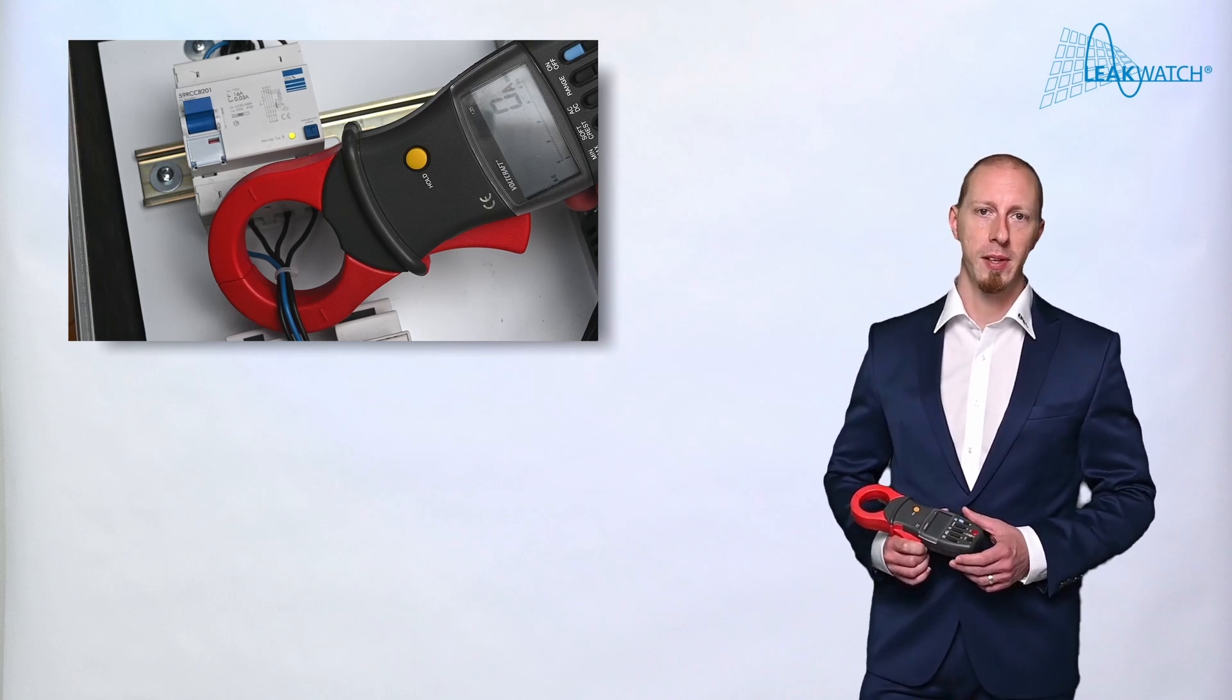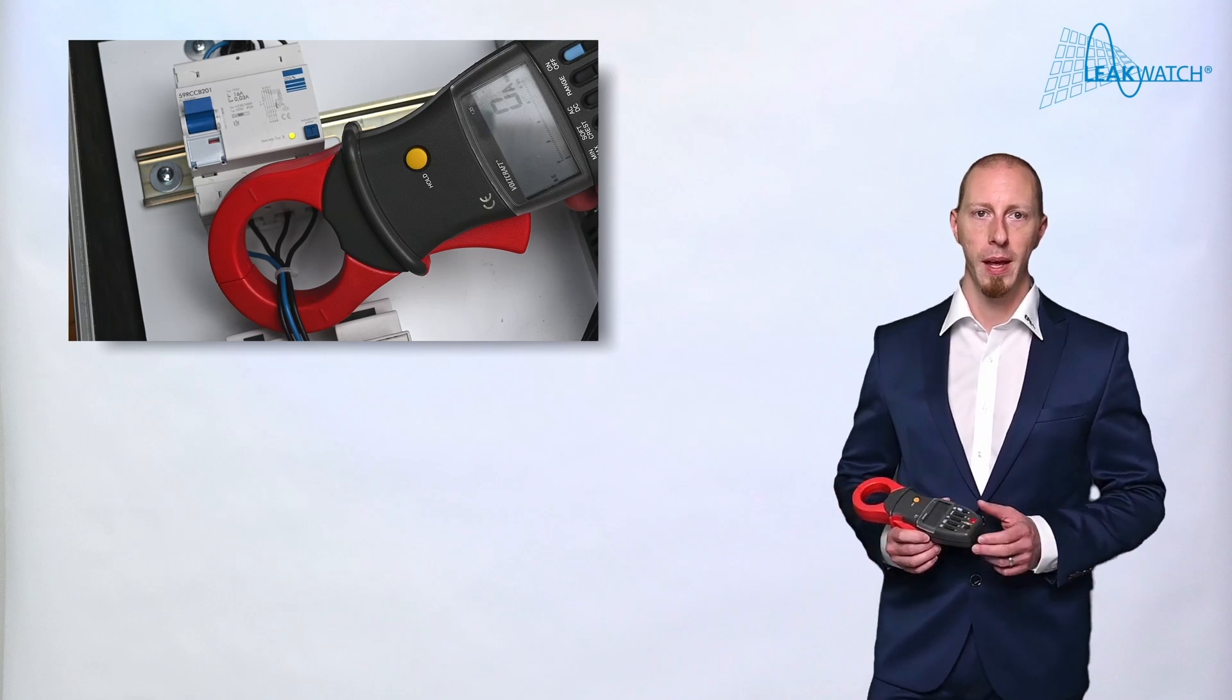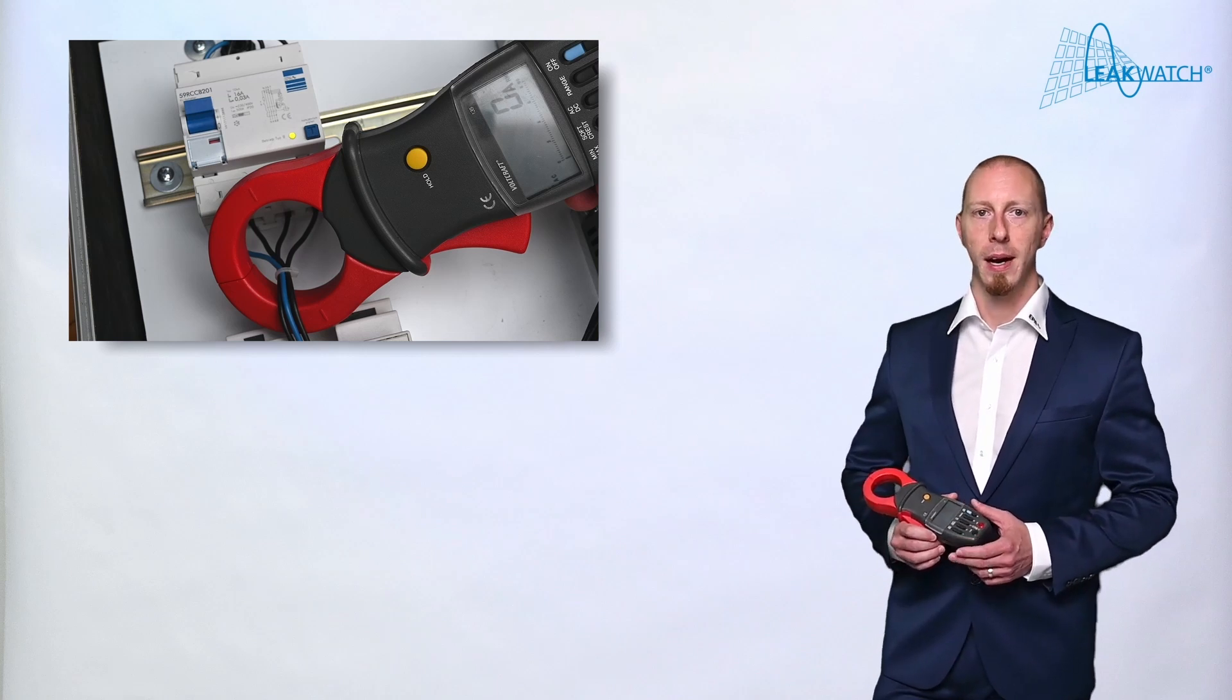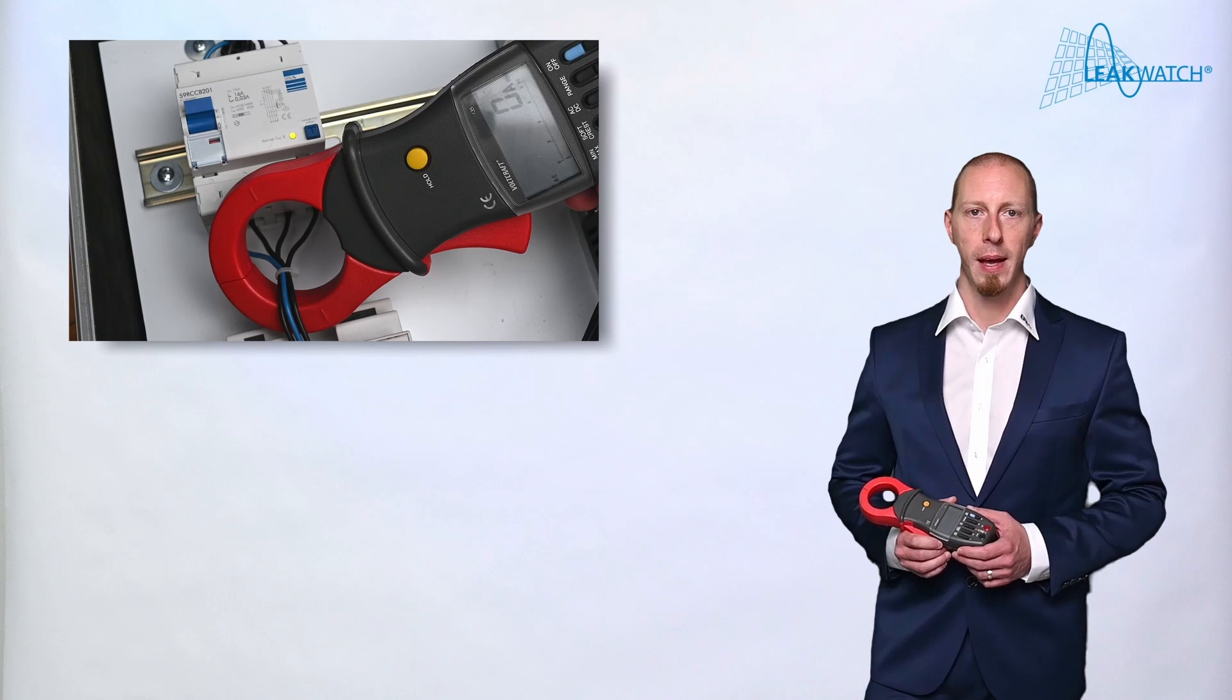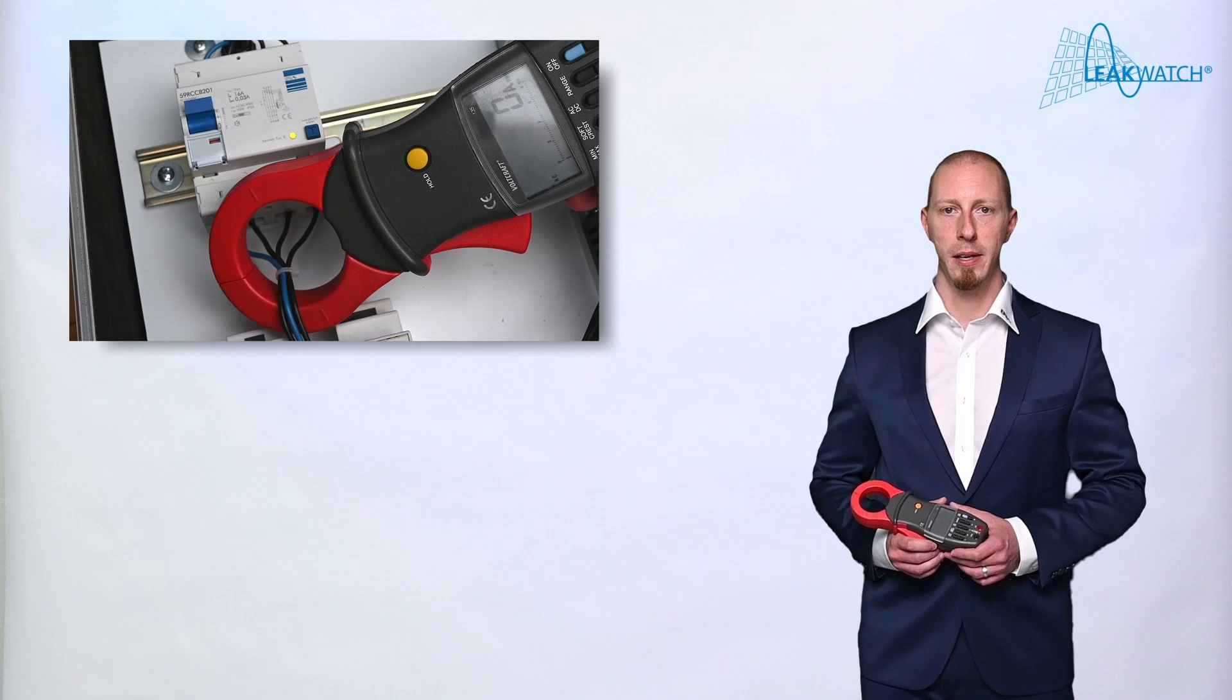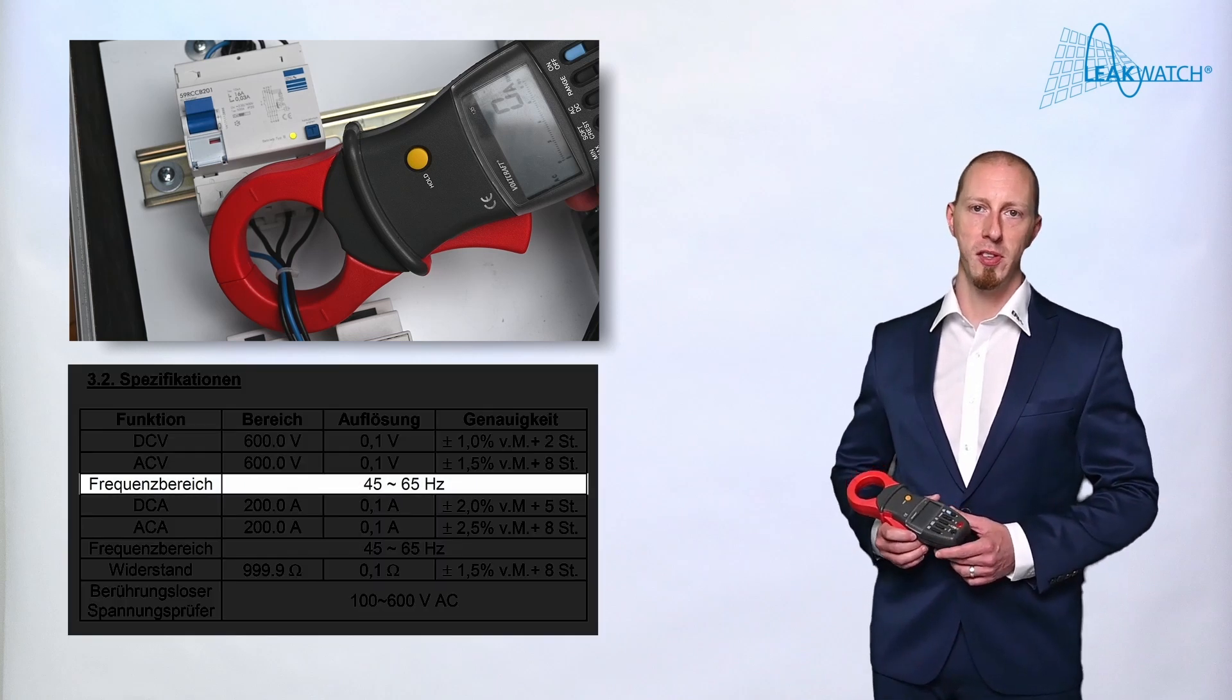However, the choice of the measuring instrument is of the utmost importance. Let's take a normal current clamp as an example. Regardless of its measuring range, the current clamp also has a limit to the frequencies that can be measured. Unfortunately, the measuring range is not always marked on the device. However, a look at the instruction manual shows that our current clamp can only measure up to 65 Hz.